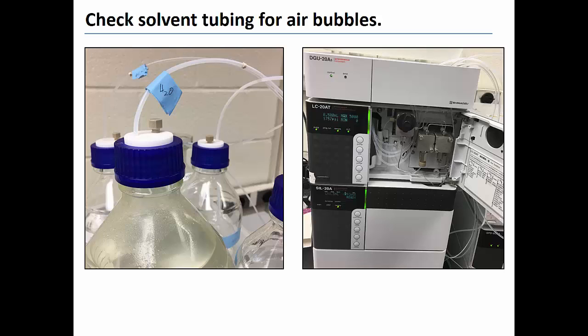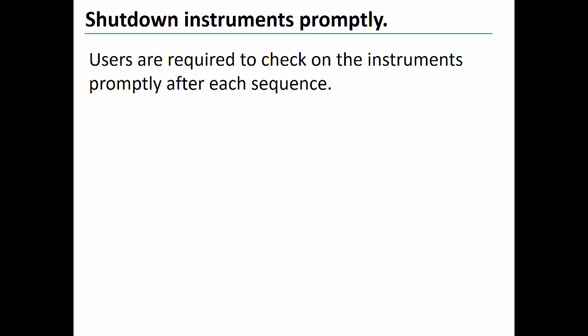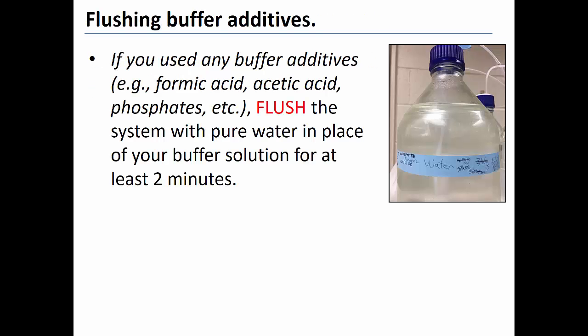It is the responsibility of individual users to ensure that the instrument is properly and promptly shut down at the conclusion of each batch. Users should estimate the total time it will take the instrument to process their entire batch and then check on the instrument promptly at or near the end of the analysis. If your method includes a mobile phase with a buffer additive such as formic acid, acetic acid or phosphate salts, you must flush the system with pure water in place of the buffer solution at the end of each batch for at least 2 minutes.